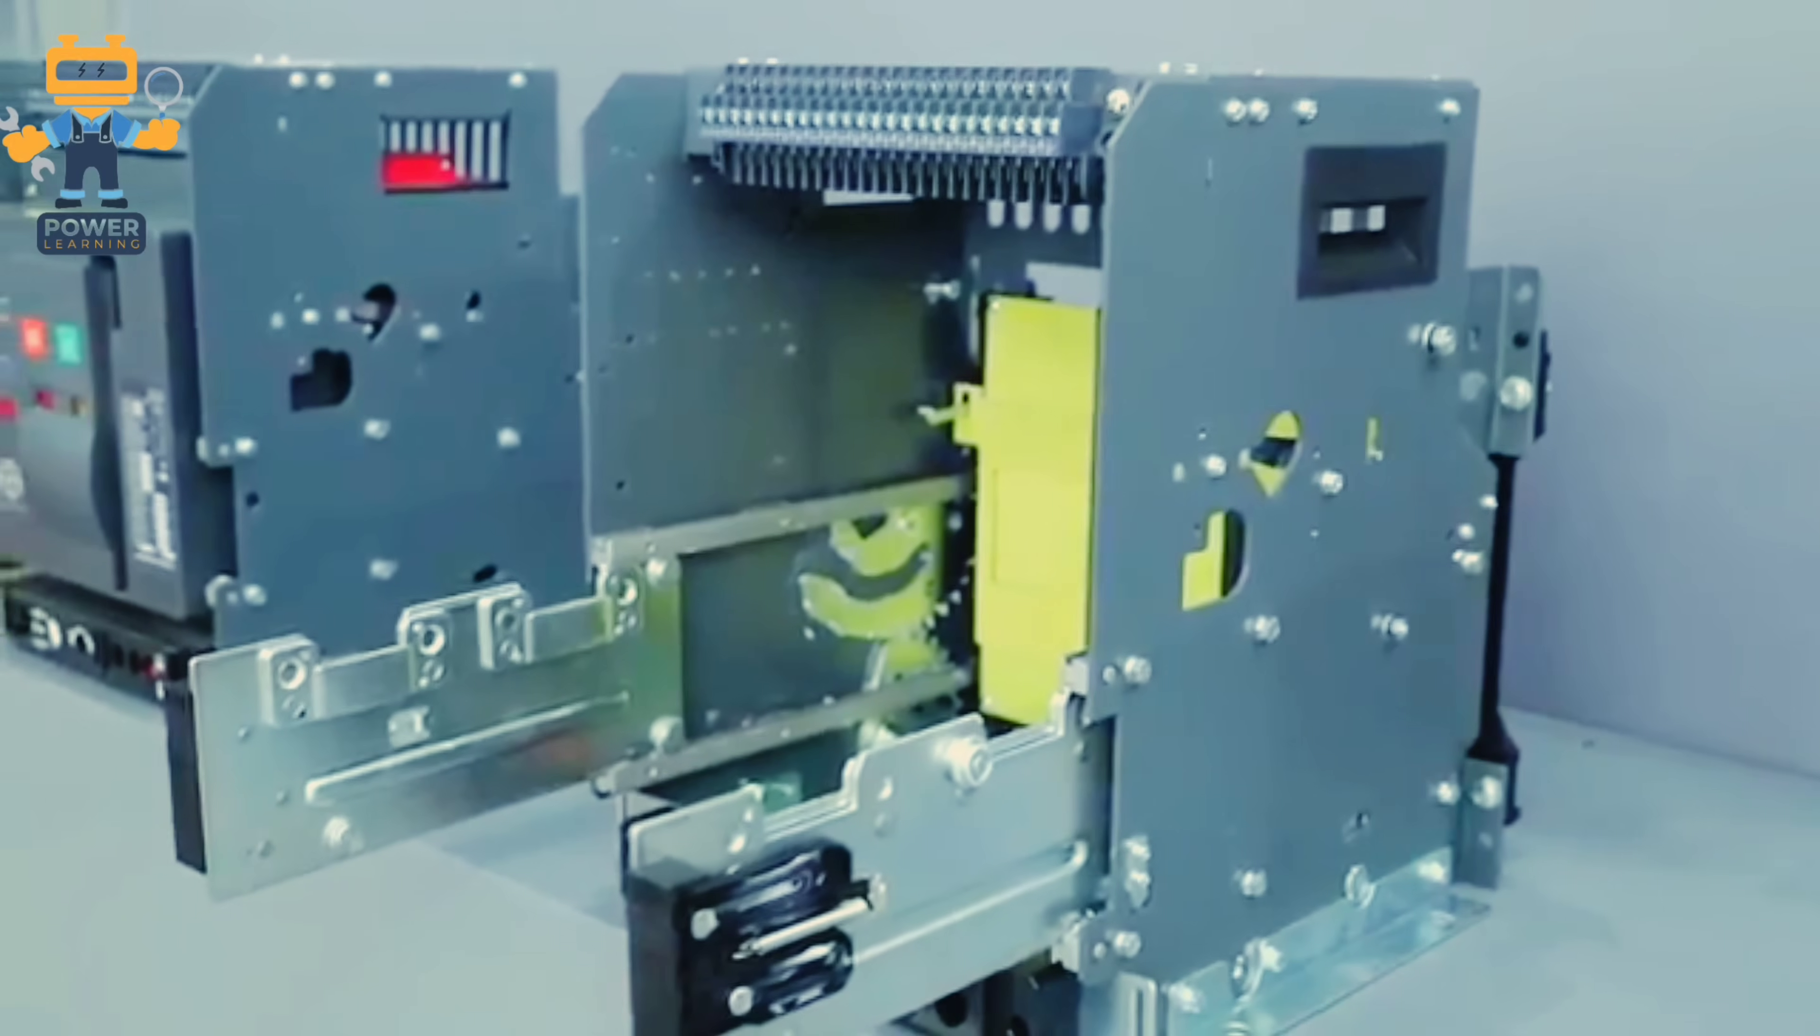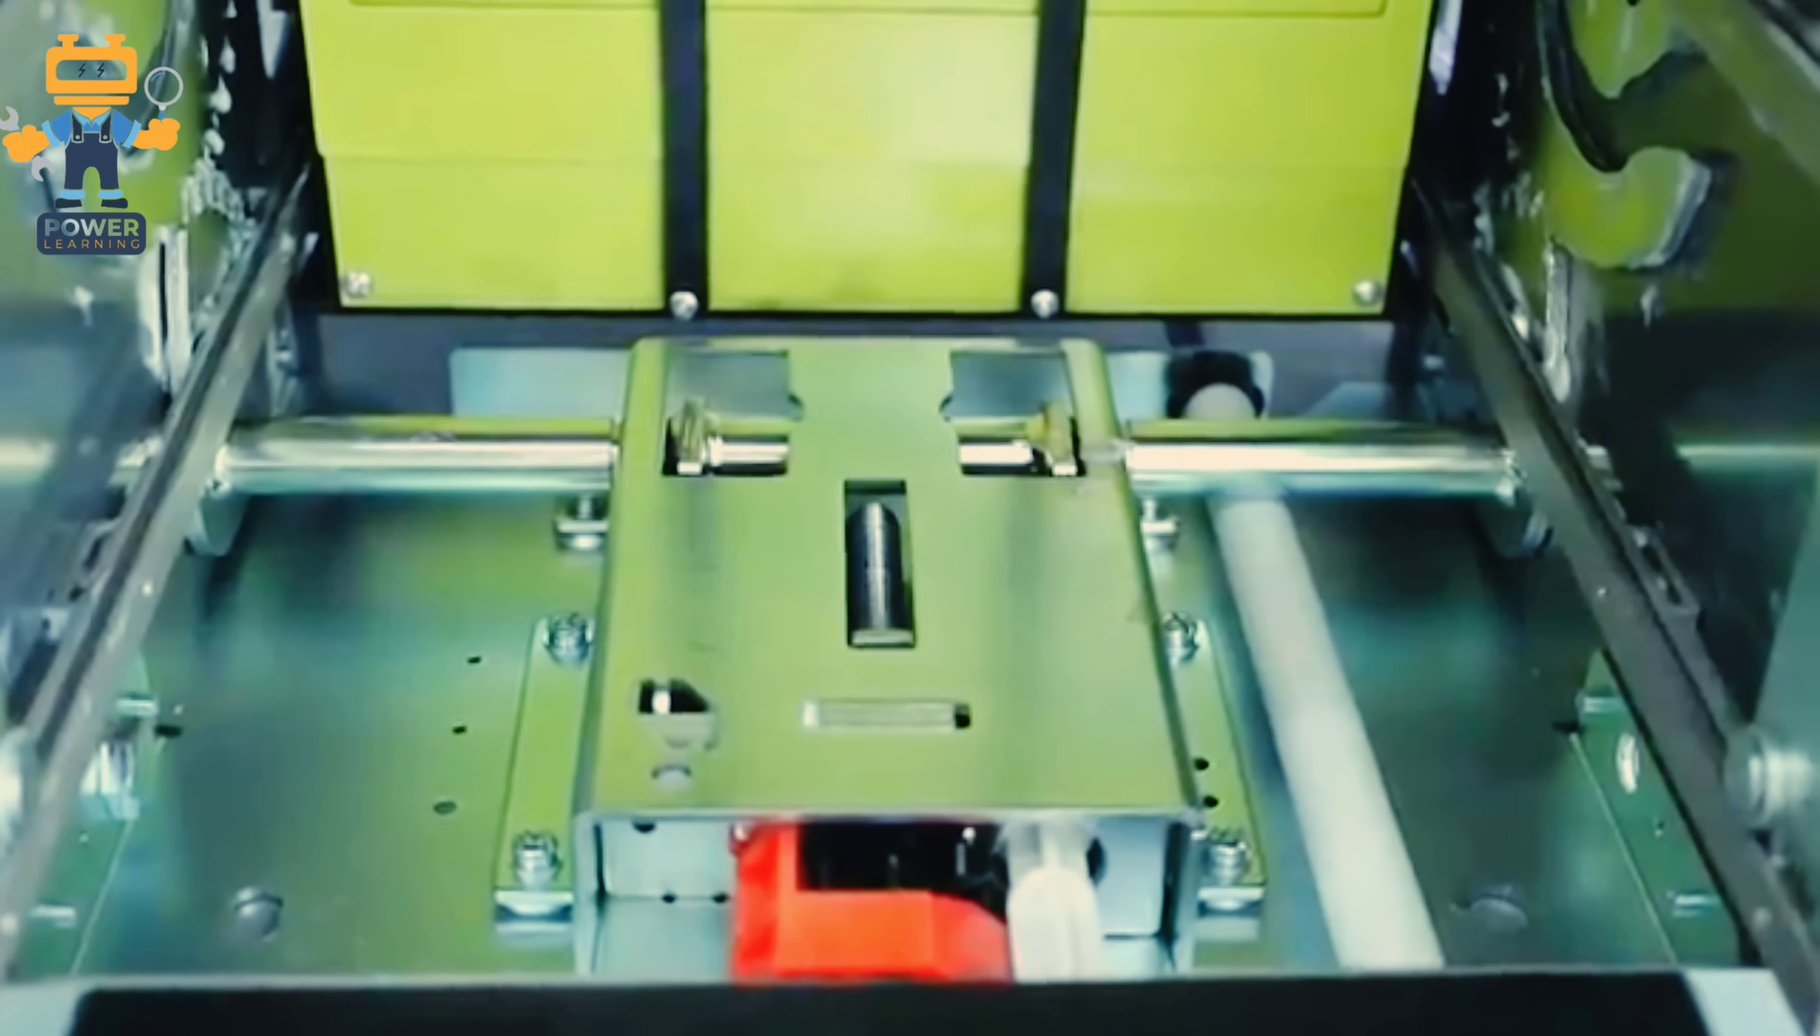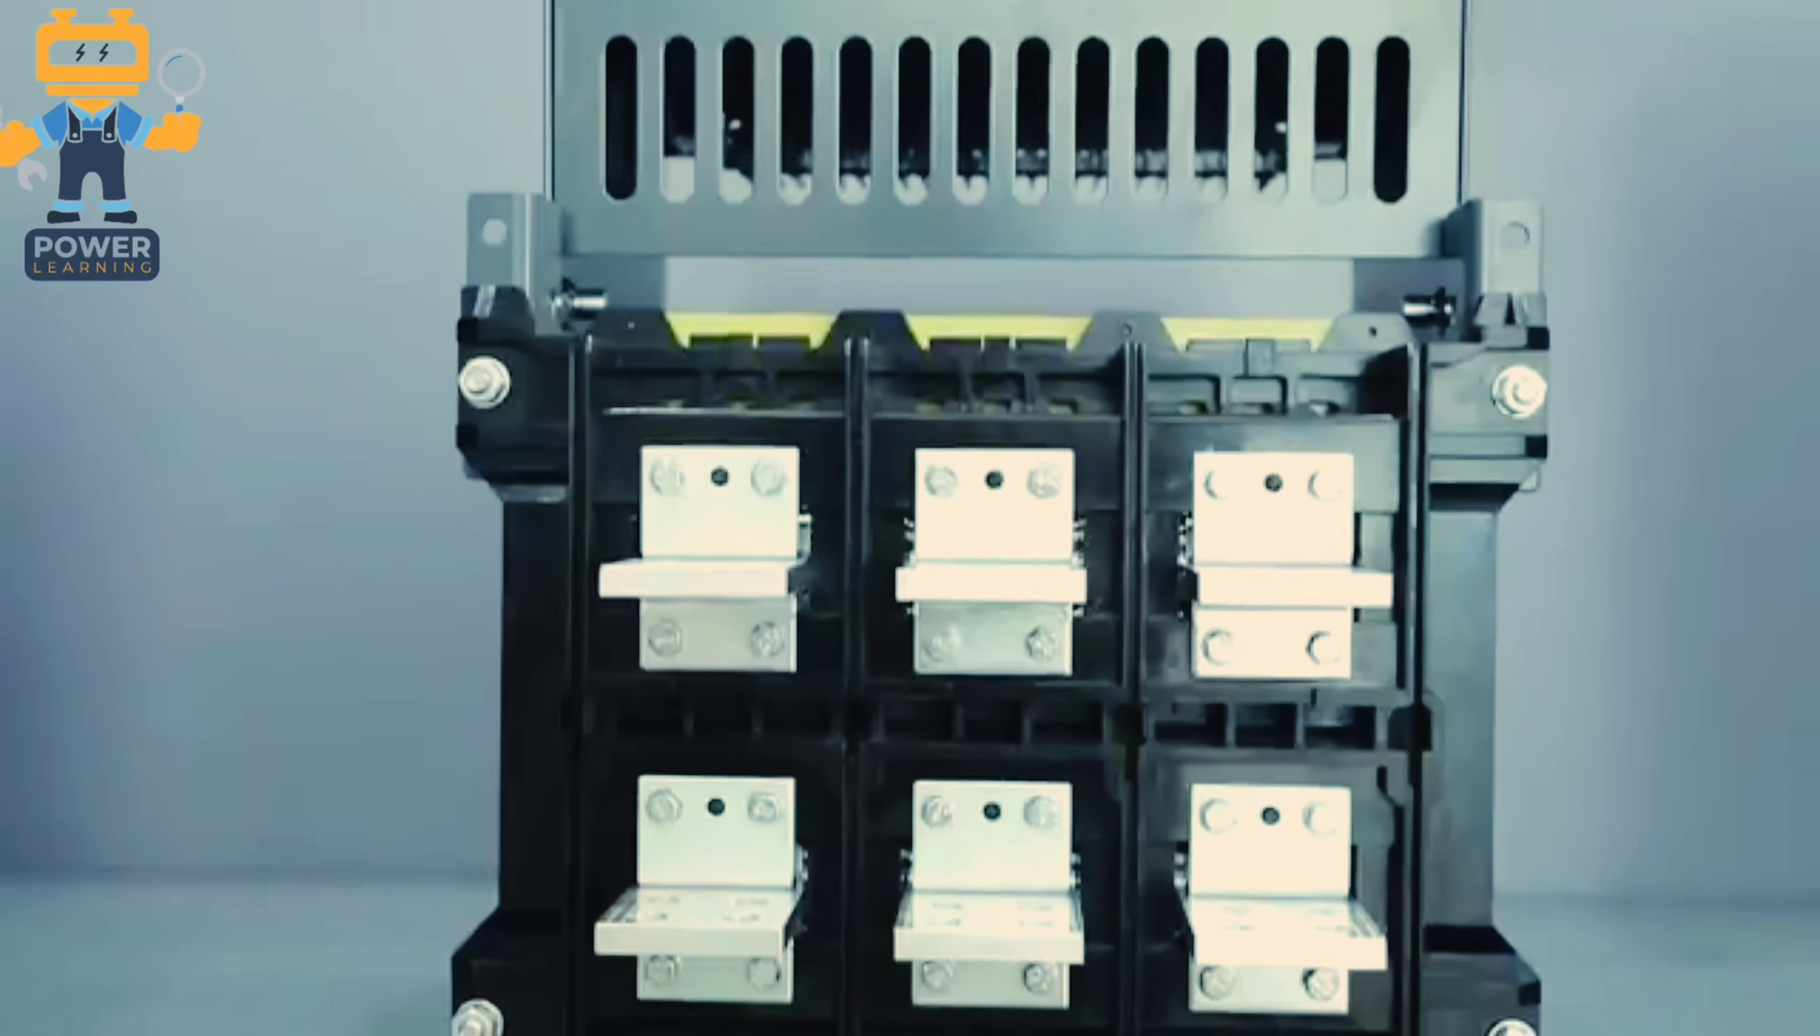This kind of ACBs we have two types of breakers. One is fixed type and one is removable type. Removable type we call draw-out, and fixed type which is fixed inside the frame. Draw-out type we can remove easily, and fixed type we cannot do it without removing the bus bars.